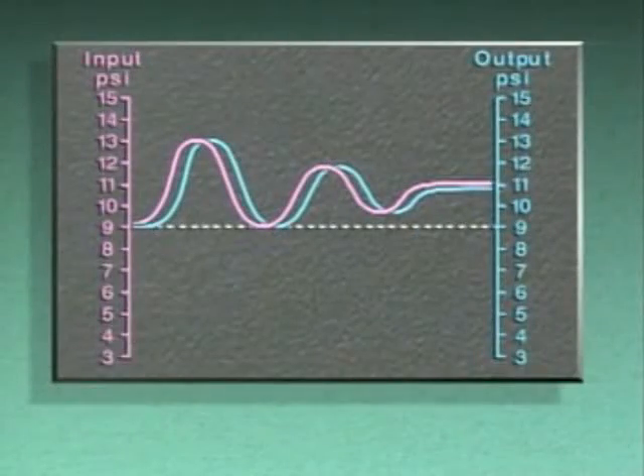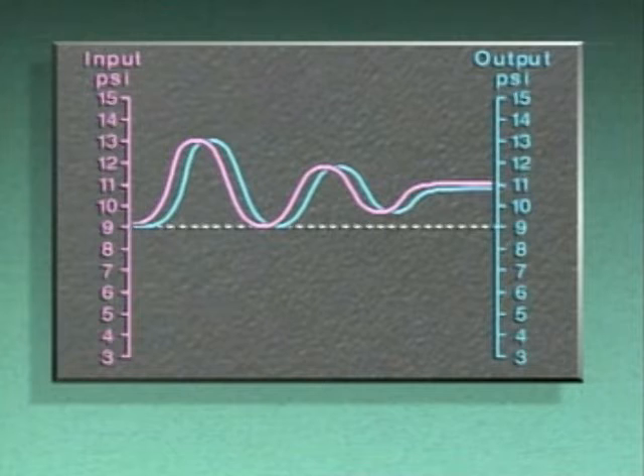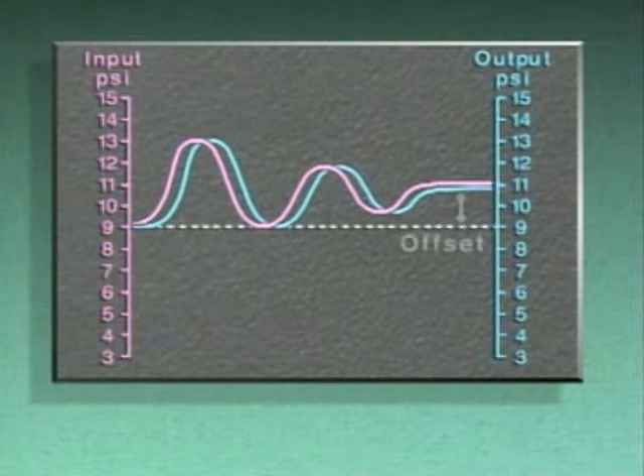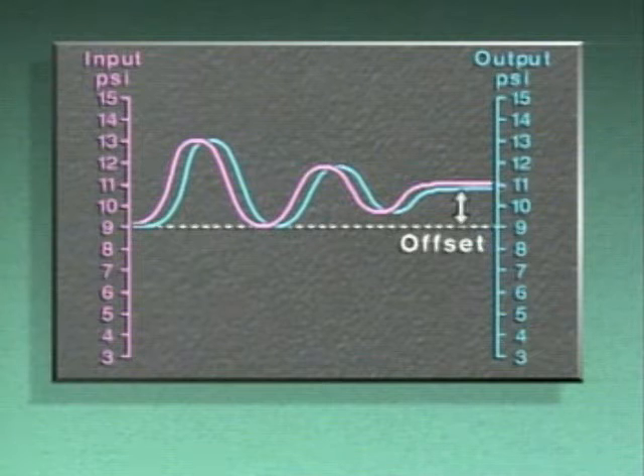Offset occurs because a proportional controller produces only enough output to bring a process back under control during a continual disturbance. It may not produce enough output to overcome the disturbance and return the process variable to its original set point. In some processes, a proportional controller may not return a process variable to its original set point. In other words, the controller's action may result in offset.